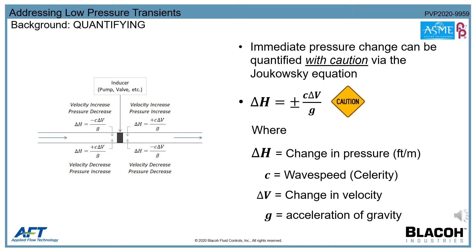Quantifying the extent of a transient pressure rise or fall begins first with the Joukowsky equation. Note: the greater the system's wave speed or the greater the change in velocity, the larger the surge impact will be. Also note, the direction of pressure change is relative to the direction of the initial flow to the inducer. For example, in the case of a pump start, the fluid velocity increases, causing a low pressure transient at the inlet of the pump and a high pressure transient at the outlet.